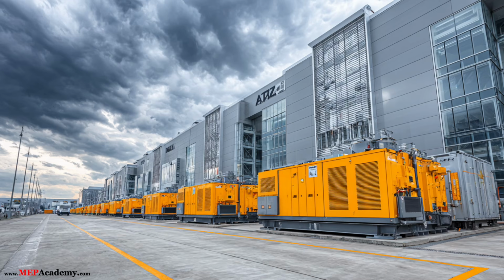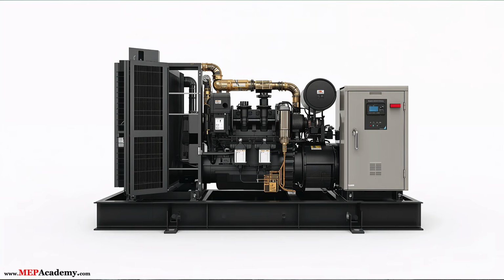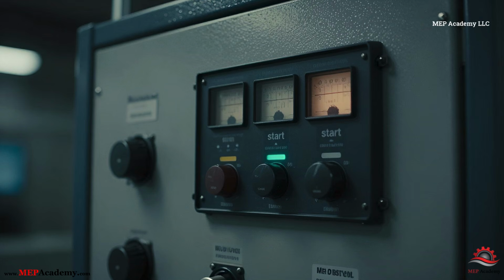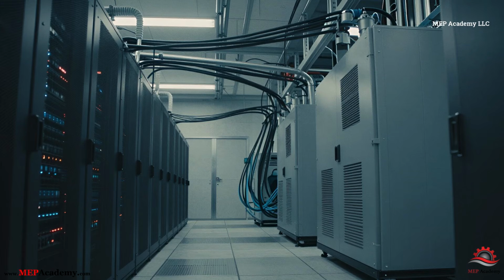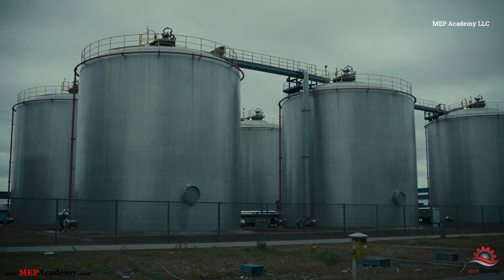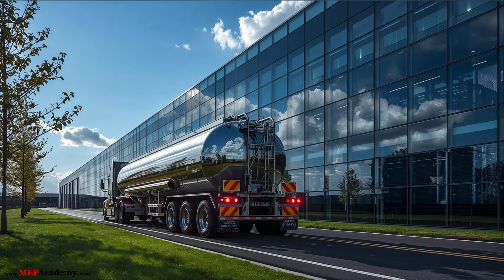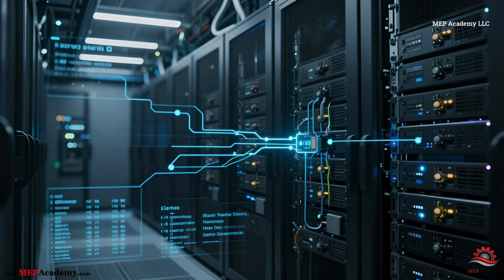And that brings us to the large engines you often see outside data centers: backup generators. Most large data centers use diesel generators that can produce several megawatts of power. When utility power fails, these generators automatically start and typically reach full output in less than a minute. Once the generators are running, they take over the electrical load and continue powering the data center for as long as fuel is available. Some facilities store enough fuel on site to operate for many hours or even several days. With fuel deliveries, they can run even longer during major outages. This layered approach, utility power, UPS batteries, and backup generators, ensures that servers continue running even during major electrical disruptions.